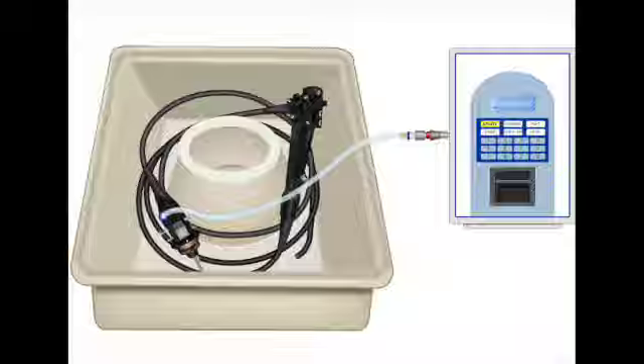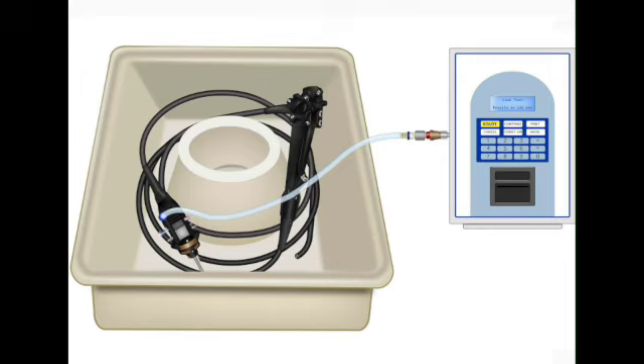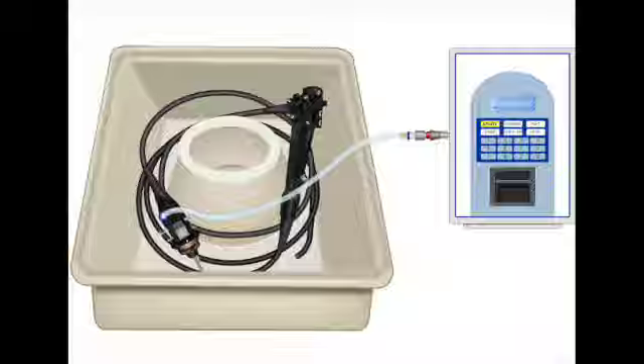That makes sense. Okay, now for the one that sounds a little risky given everything we've said, the wet manual leak test. Submerging it in water. It does sound risky, but it's a very old and effective way to find the exact location of a leak. You can see the bubbles. So what's different about the prep here? Again, remove all the detachable parts. But, and this is a key detail, if you're working with a specialized scope, like an ERCP or an EUS scope. Right, the really complex ones for pancreas and bile duct procedures. Exactly. Those have extra ports and electronics at the end, so you must put a special water-resistant cap on before it goes in the water.